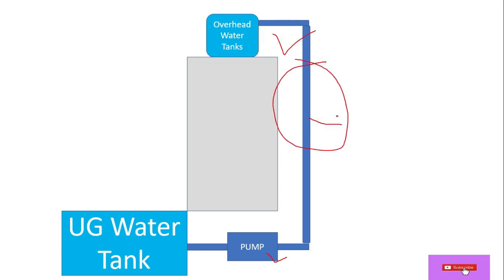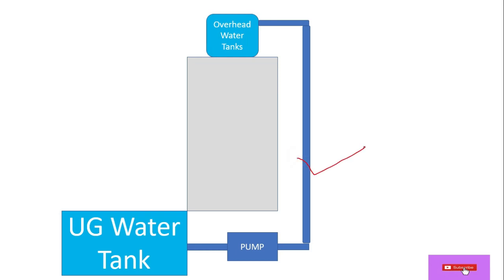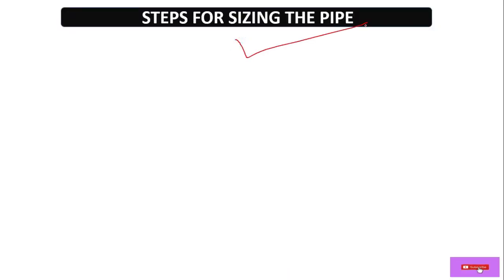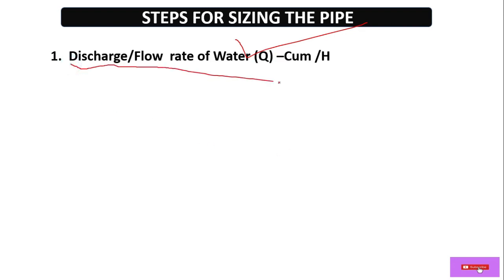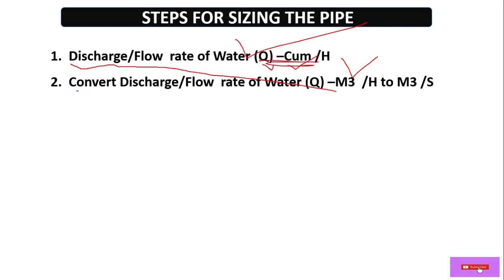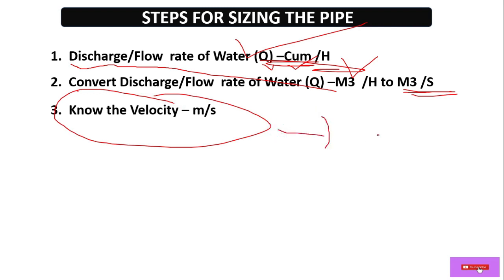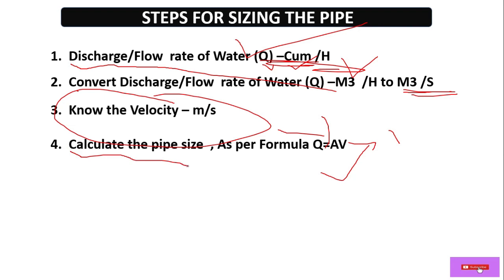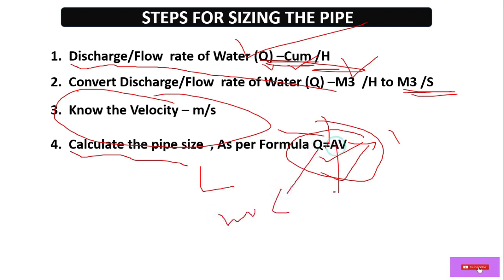This is the pipe from the pump to the overhead tank, and we are going to calculate the pipe diameter — the pipe size. To calculate the pipe size we follow some steps: first, know the discharge or flow rate Q in cubic meters per hour; then convert to cubic meters per second; then know the velocity of the water flowing through the pipe; and finally calculate the pipe size using the formula Q = AV, where Q is discharge, A is the cross-sectional area, and V is the velocity.